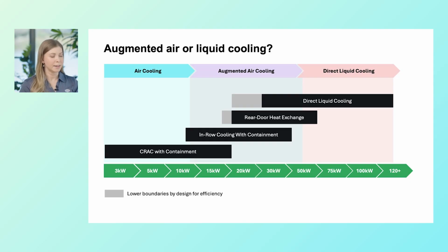Yeah, absolutely. I'd say we absolutely can accommodate higher density with air cooling. There are other technologies we can use. Some of the densities we're seeing even in previous chipsets aren't necessarily requiring liquid cooling. The GB200 was actually the first one that 100% requires liquid cooling. Previous chipsets, you could go either way, liquid cooled or air. But even the air cooled servers with those chipsets are very high density.